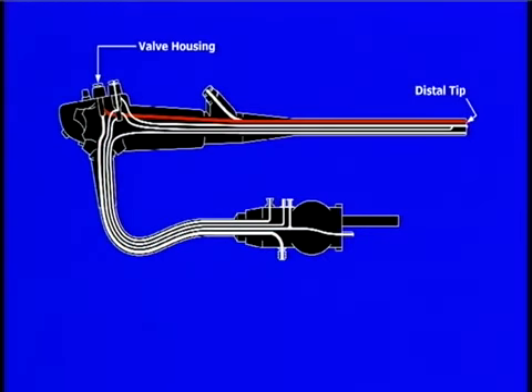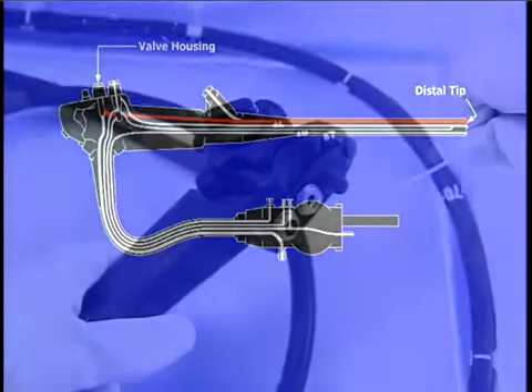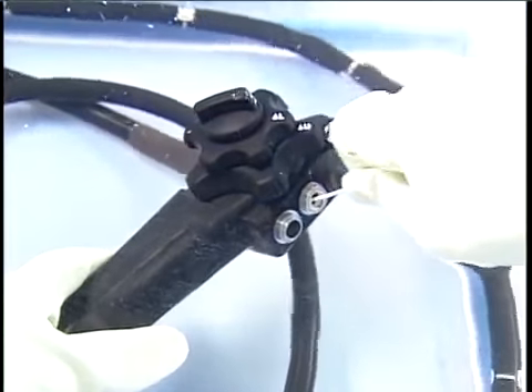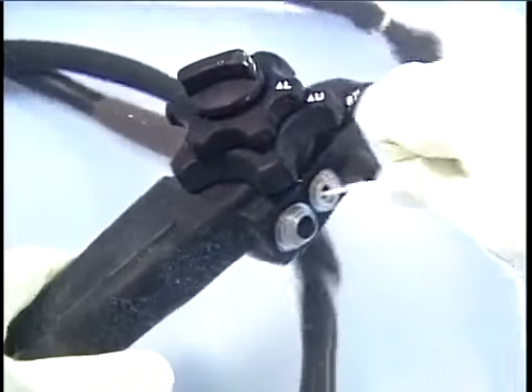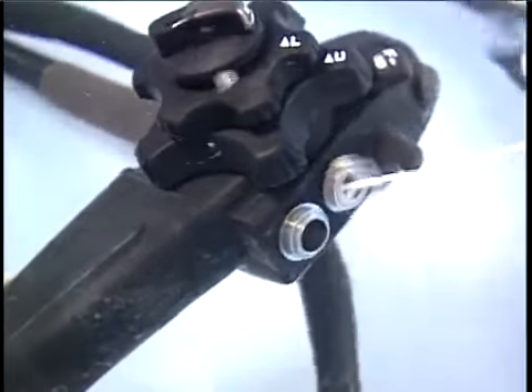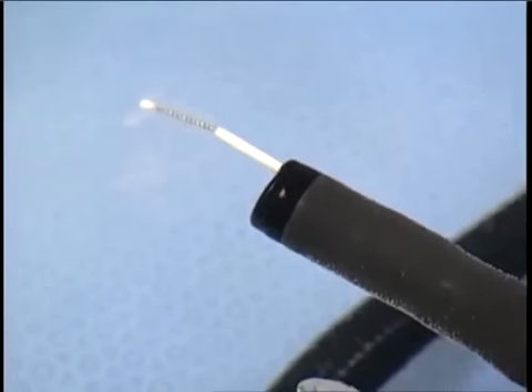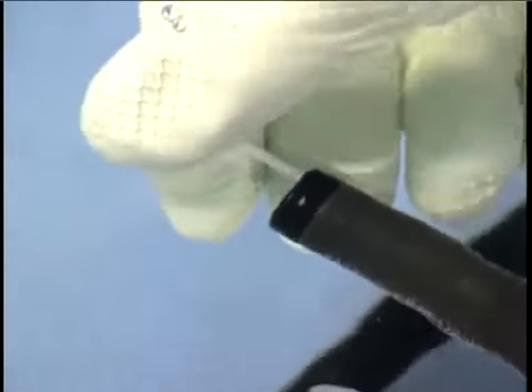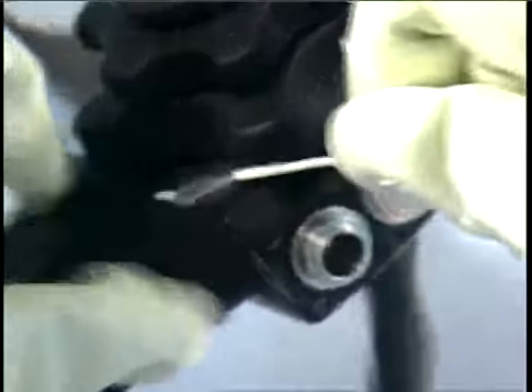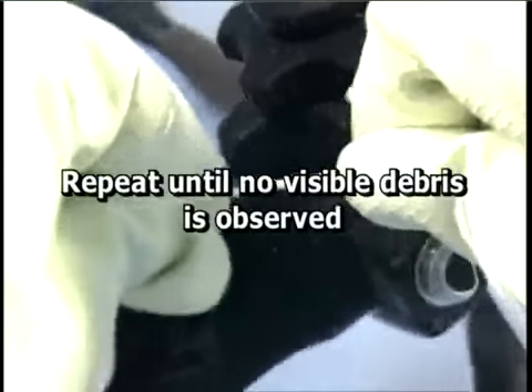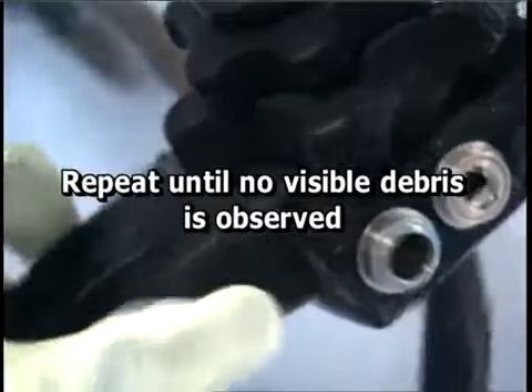To brush the suction channel within the insertion tube, hold the channel cleaning brush at a 45-degree angle and insert the brush into the opening in the side of the suction valve housing. Use short strokes to advance the brush through the insertion tube until it emerges from the distal tip. Remove any debris from the bristles with your fingers and gently pull the brush back through the channel. Inspect and clean the bristles again. Repeat this process until you cannot see any further debris on the bristles.